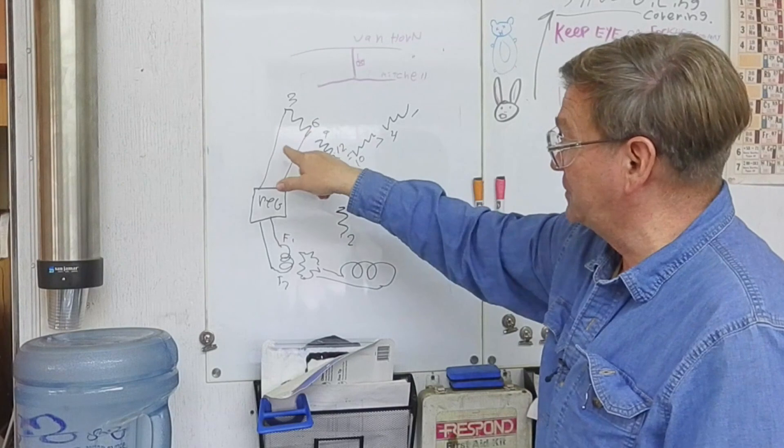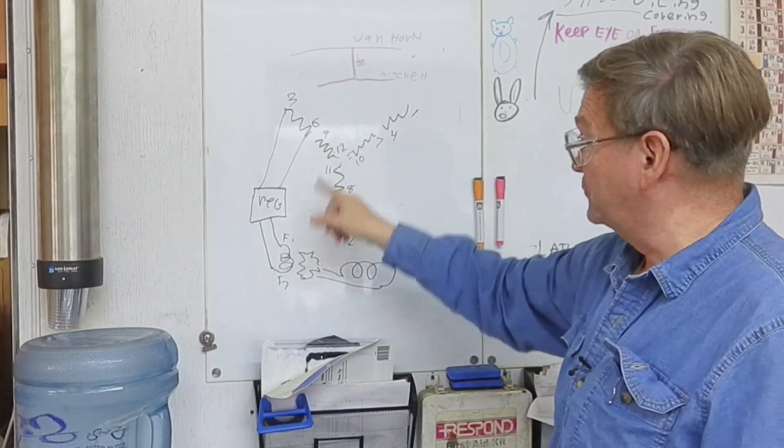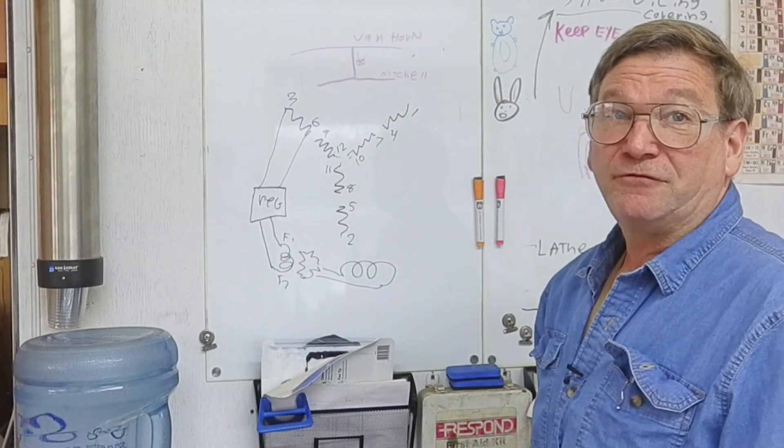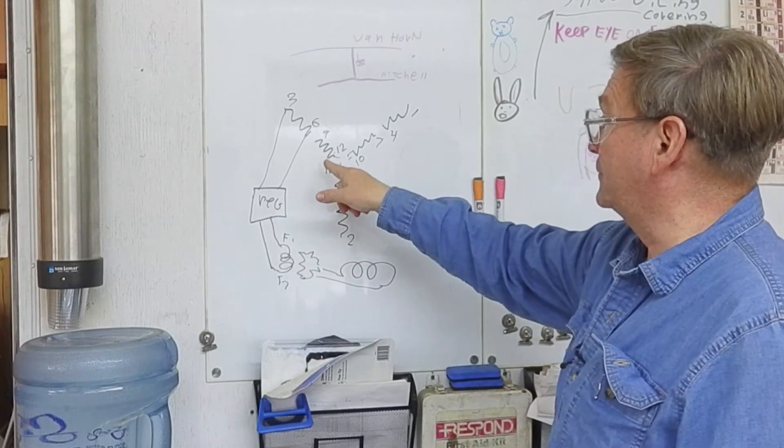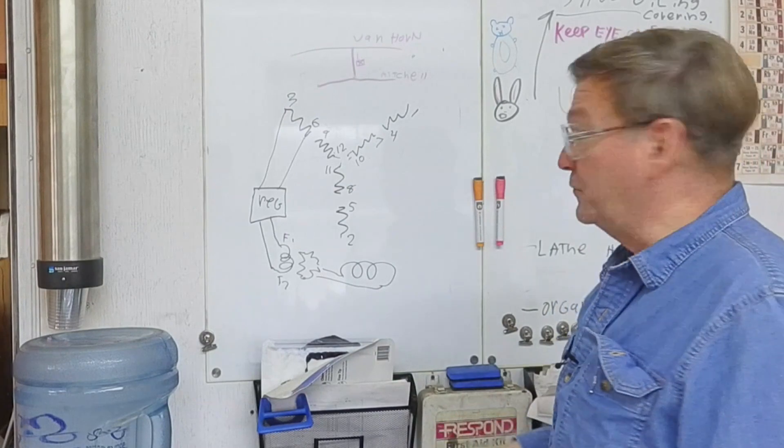Sometimes you'll also have to tie in. Not necessarily three six. That was just the easiest on the drawing. Could be any one of the coils. If you found one that was a 240 volt input for your regulator, of course, you'd have to have a set that was coming off of 240, however you wired it.